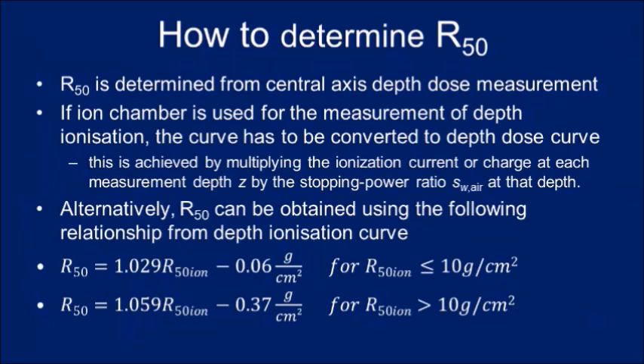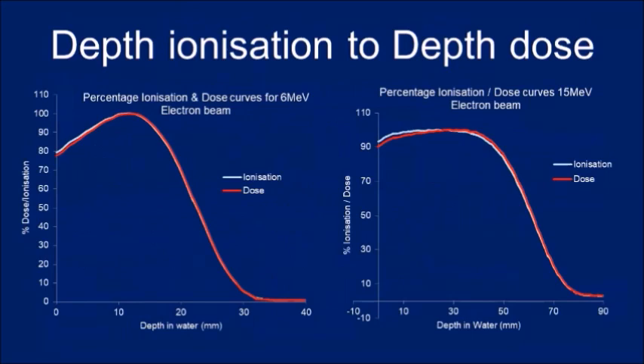To convert depth ionization to depth dose when using an ion chamber, multiply the ionization at each depth z by the stopping power ratio s_w,air. Alternatively, empirical formulas from TRS-398 can be used: for low energies R50(dose) = 1.029 × R50(ion) − 0.06, and for high energies use 1.059 and 0.37. Most commercial water phantom software automatically performs this conversion from depth ionization to depth dose.